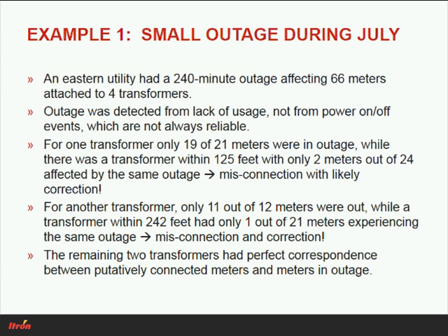This is very low tech. It can be automated, of course, and we have. So you get a list of which meters are likely misconnected, and it doesn't require any fancy data. You are simply looking for when the power is out, and you don't even look for power off and power on events. You're simply looking for zero energy, which rarely happens if the meter has power.